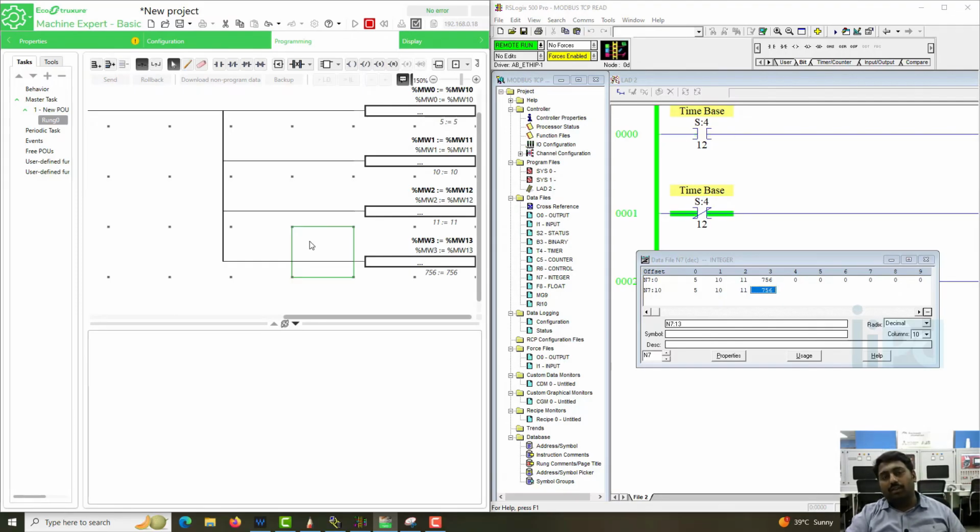Sorry, from the client. So from here the client is the Modbus master, and the server is the Modbus slave. Okay, so you can read any number of devices like this, but as I recommended, if you are going to read intermittent registers, like you need to read 10, then there is a gap of 2 and you have another 10, it's better to read the 22 together instead of putting it as 2 different instructions.